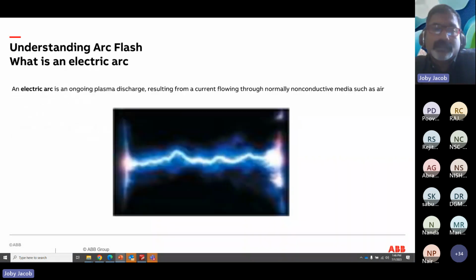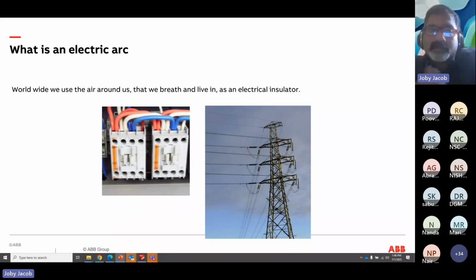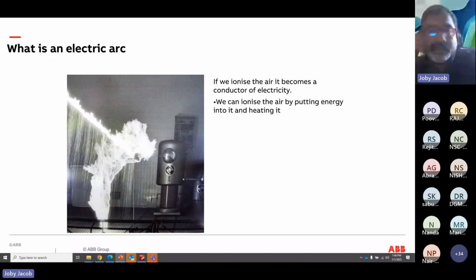An electrical arc is an ongoing plasma discharge resulting from a current flowing through a normally non-conductive medium such as air. So what happens if you have two conductors and increase the voltage between them? Air is supposed to be an insulation medium, but as the voltage rises, the air starts breaking down, it ionizes, and it becomes a conductor of electricity.